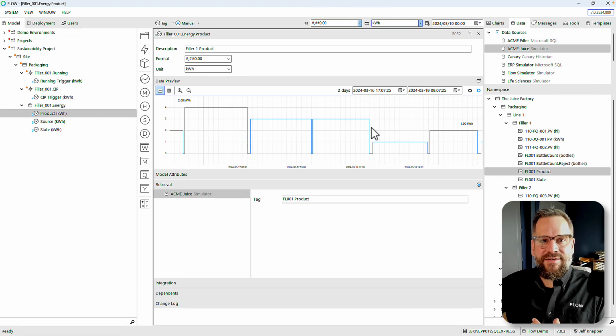When we connect to these databases, we're helping normalize time so that when we want to cross-reference historian tags or real-time data tags and data that's in SQL, there's always a timestamp alignment. So we actually carry those timestamps from the SQL data. Whenever it changes, we assign a new timestamp and carry that value down when we compare it to historical data. Really makes it easy to work with the data when we're basically presenting it in that standard historian tag format to your users.